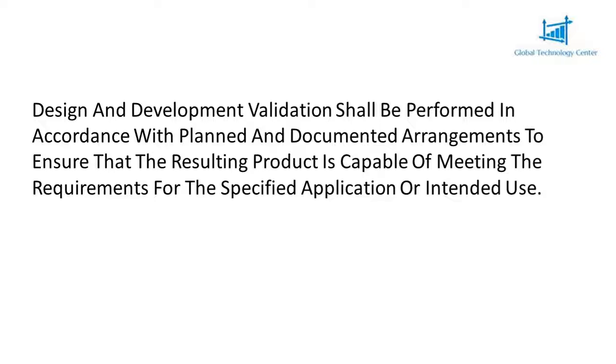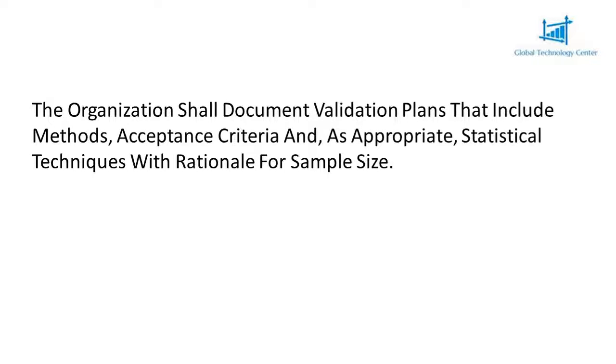Design validation shall be performed in accordance with planned and documented arrangements to ensure that the resulting product is capable of meeting the requirements for the specified application or intended use. The organization shall document validation plans that include methods, acceptance criteria and, as appropriate, statistical techniques with rationale for sample size.